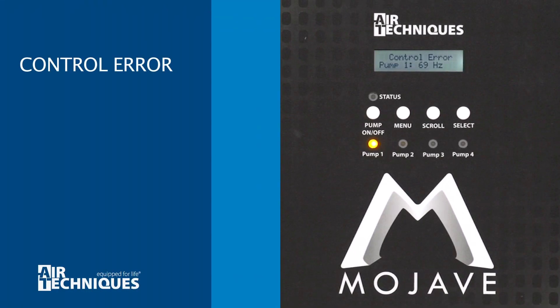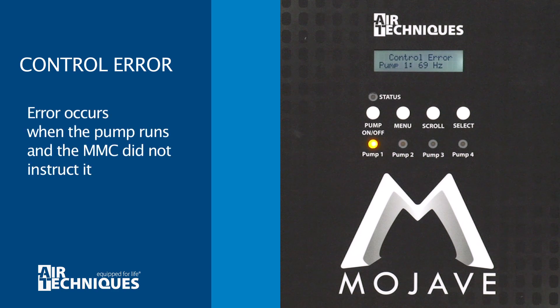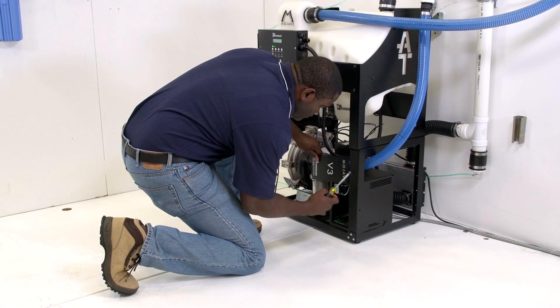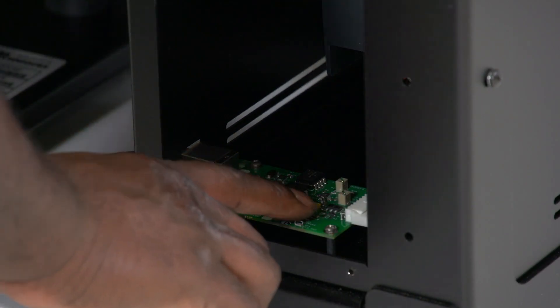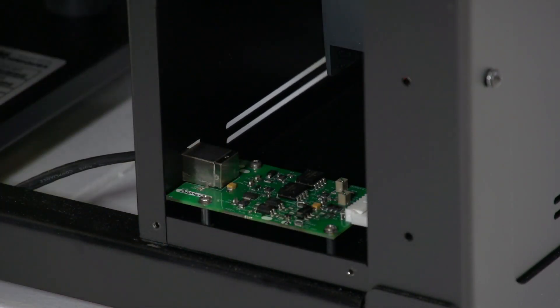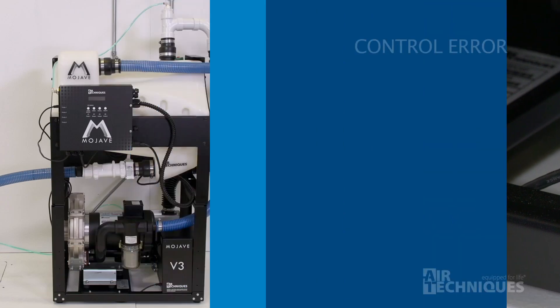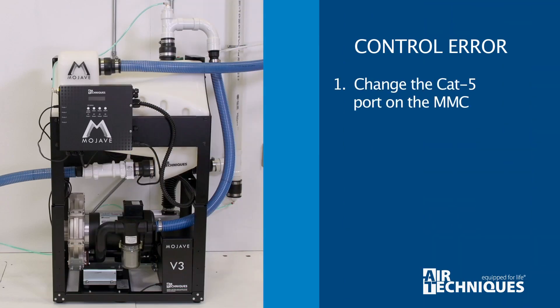The control error occurs when the pump is running and the MMC did not instruct it to run. Check the bypass switch and ensure that it is in the off position. If the problem continues with the bypass switch in the correct position, change the port on the MMC that the CAT5 cable is connected to. If this doesn't stop the error, change the CAT5 cable.